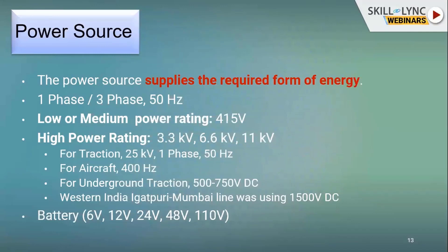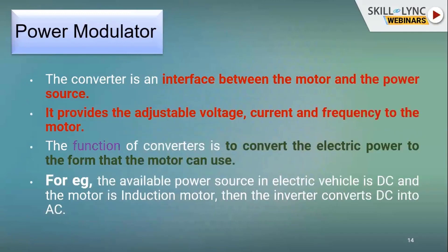For traction, 25 kV single-phase 50 Hz is used; for aircraft, 400 Hz supply is required; for underground traction, 500 to 750 V DC is used. The Mumbai–Igatpuri line in western India was 1500 V DC but has since been converted to AC. For DC power sources, different batteries like 6 V, 12 V, 24 V, 48 V, and 110 V are used — batteries are mostly used in electric vehicles. The power source and motor selection determines which power modulator to select.